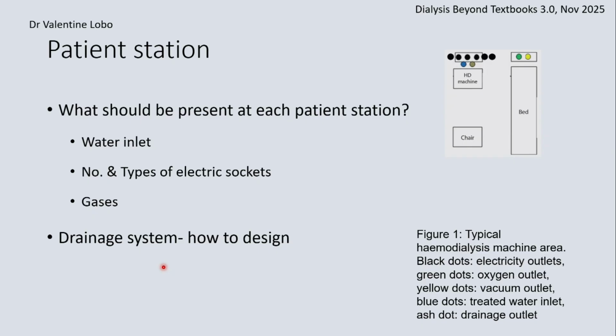As far as the drainage system is concerned, just before that, what type of electric sockets do our machines require? Good. Each and every socket should have both 5 and 15 amps. Dialysis machines take 9 to 10 amps of power, so you need a 15 amp socket for a dialysis machine. Most other medical equipment, including ventilators, take about 500 milliamps of power, so a 5 amp socket is good enough for most. But today, because you can get 5 and 15, I would have all my sockets as both 5 and 15.